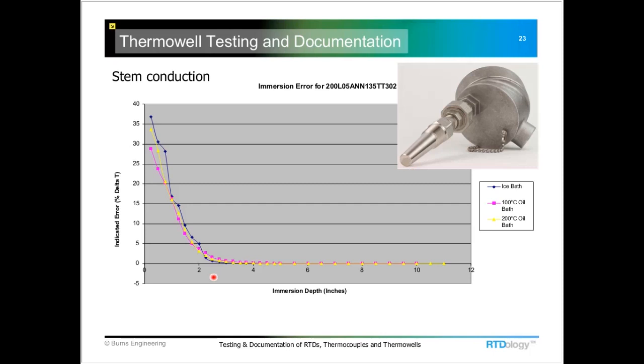So if we look down on the immersion length, we can see right about this, 2.5, 3 inches of immersion. Most of that error has gone away. If we use something shorter than 2 inches, we have some fairly large errors here. And if we get out to 4 inches and greater, the error is pretty much completely gone.